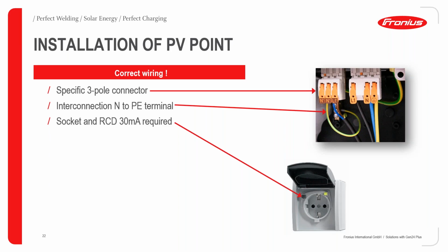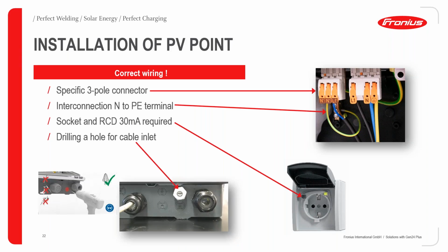So when it comes to the installation of the PV point, it's very simple. On the actual GEN24 Plus, we have a separate outlet on the inverter, which is dedicated for the PV points. So this outlet, as you can see, you will have your neutral, and L1. Your L1 and your neutral will go to your load, whereas your other neutral will then be earthed to the earthing of the inverter. The only thing you need between this outlet and your loads should be a socket with an integrated RCD, or you can have a socket with an external RCD. And the RCD, which is your residual current device, we recommend that this RCD should be 30 milliamps rated. And that is just a safety feature.